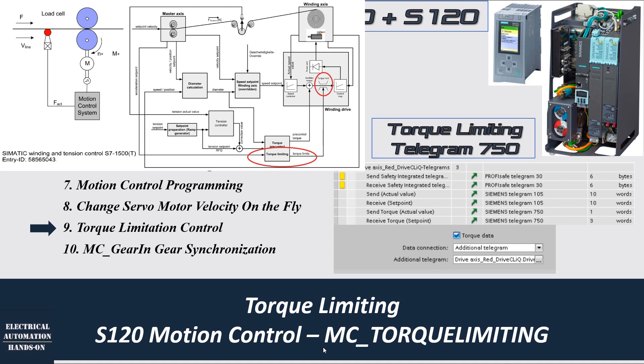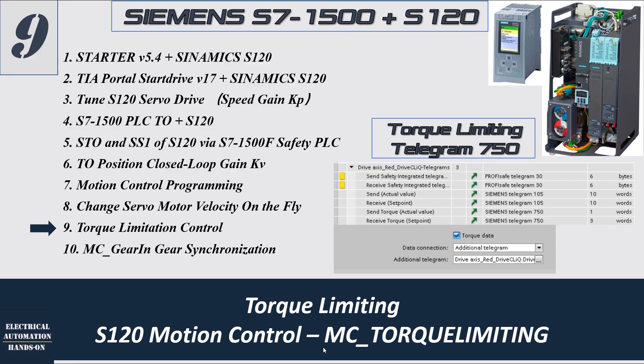The typical application when we use torque limitation is winder control. For example, when we control the winder in velocity control mode, we can involve torque limiting. We can set a certain upper or lower range so the force or tension delivered from the drive motor is limited. The motor may just be stuck or won't run — especially for the rewind application — so the motor can maintain the highest torque and keep the highest tension without breaking the web.